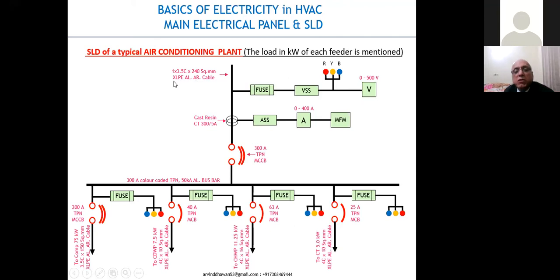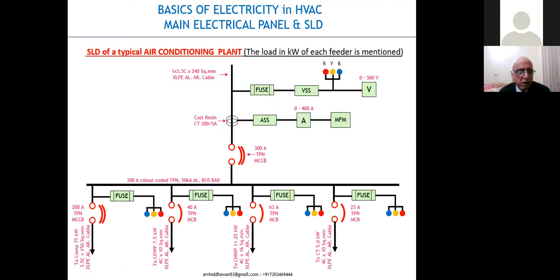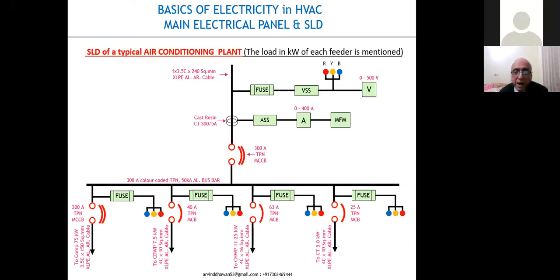You'll also come across types of cable insulation: XLPE ALAR cable. X means cross (not multiply), L for linked, P for polyethylene, E for ethylene — so XLPE is cross-linked polyethylene. AL means aluminum conductor, A-R means armoured cable. So when you're billing, you must make sure this is an armoured cable and not an unarmoured cable — there is a significant financial differential between the two.